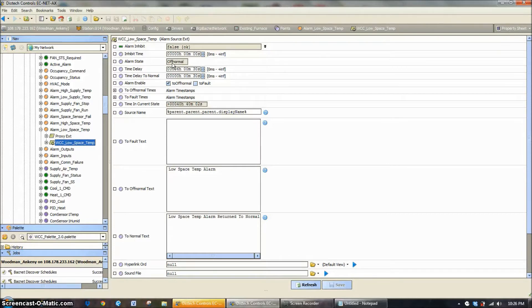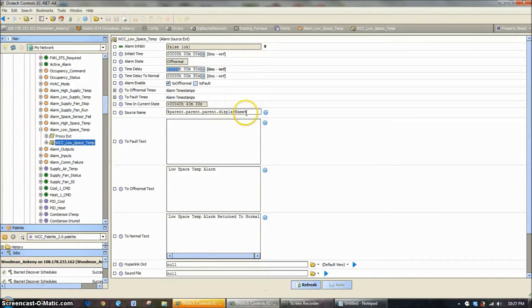Time delay is the delay from the time that the event occurs to when it's actually reported. In this case, since it was a low space temperature alarm, it was set for 30 seconds, and that is why my alarm was going off constantly. I really don't care if this alarm happens in less than four hours — it's just not that important of an alarm if we're a little bit below space temperature. If it's been below space temp for four hours, then I probably know there's something wrong with the furnace. So to make the alarm frequency go down considerably, I'm going to make this a four-hour delay. Make sure you hit Enter — it would be the same in the web interface, you would just have to hit Save.